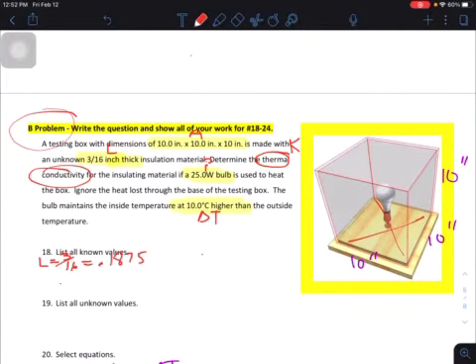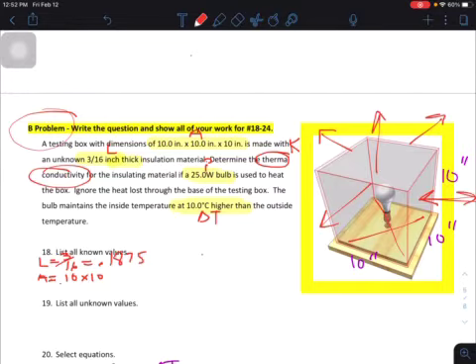We know that the area is 10 inches by 10 inches. That would give us the area of one of the walls. We've got heat going up from the top and from the side walls. There are five walls. So we go 10 times 10 is 100 times 5 equals 500 square inches.